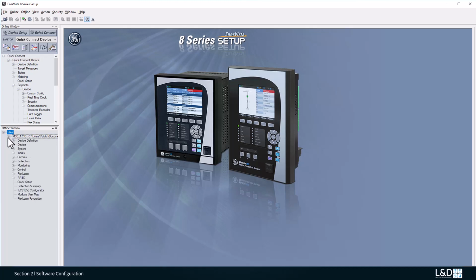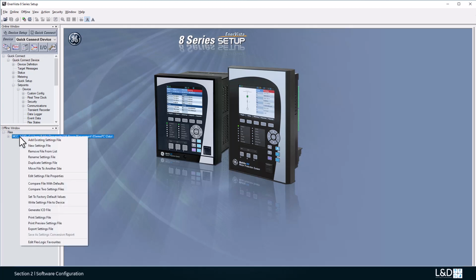And then we can see this setting file saved in this offline window. So this is the offline window setting file. And there are two ways to write this setting file back into the relay. The first is the same as the 369. You just right-click the mouse over the setting file, and you can choose Write Setting File to Device. Then it will write into the relay, same as the 369.